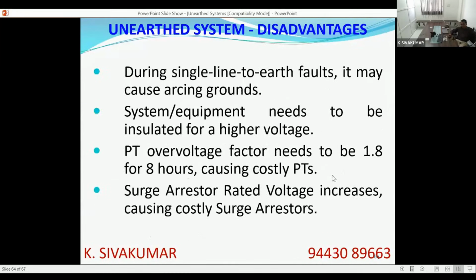And as I said, there are arcing grounds, because there is a potential jump between earth and the healthy phases. It will keep trying to strike an arc. So these arcing grounds also cause damage to insulators and terminal equipment. There are records of damages caused to terminal equipment and insulators. So this is another big disadvantage.